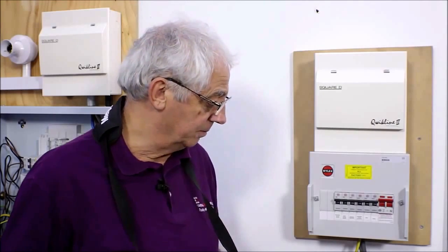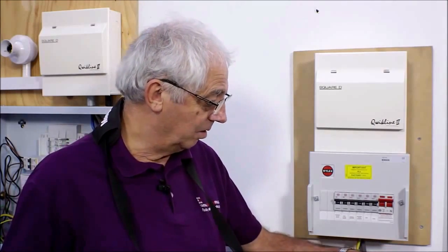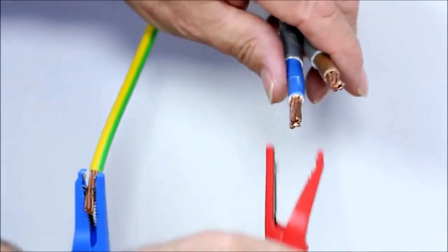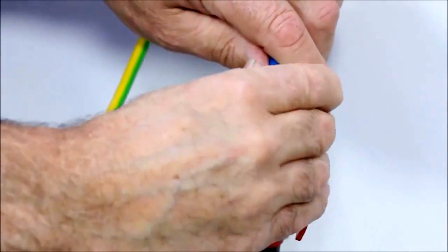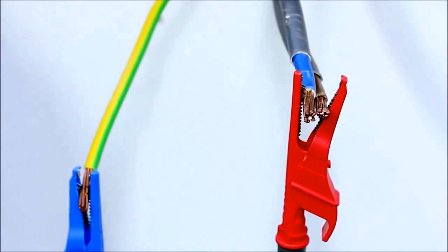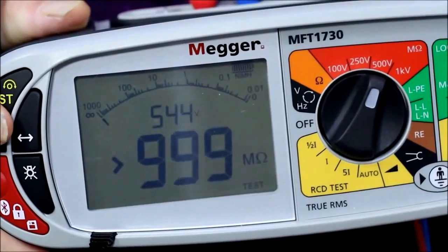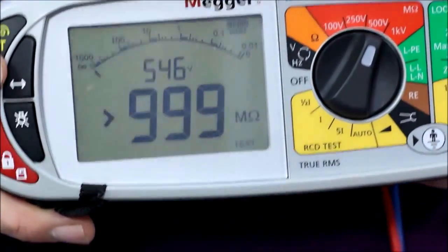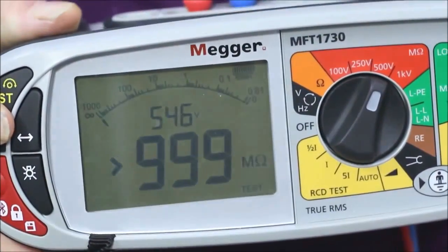Of course, rather than measure between line conductor and neutral conductor separately, I could, if I wanted to, join the two together and carry out a test like so. And if the test again is of a very high reading, there'd be little point in testing between neutral and earth and then line.